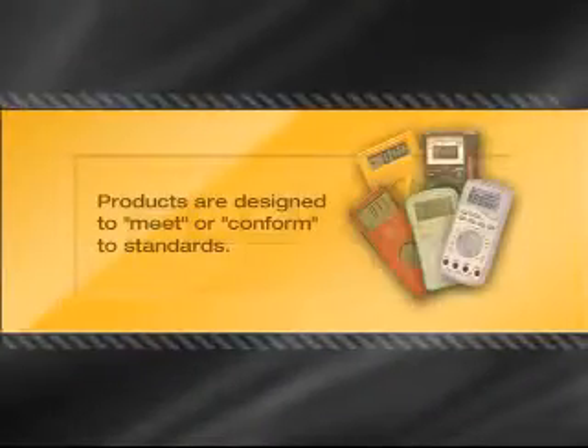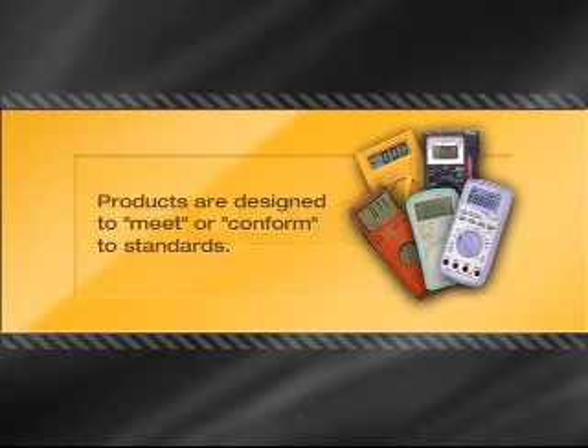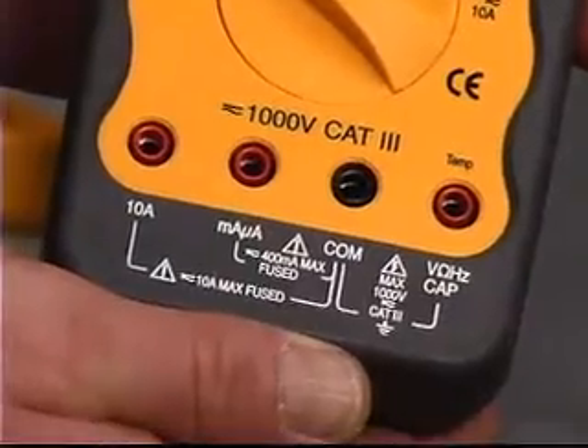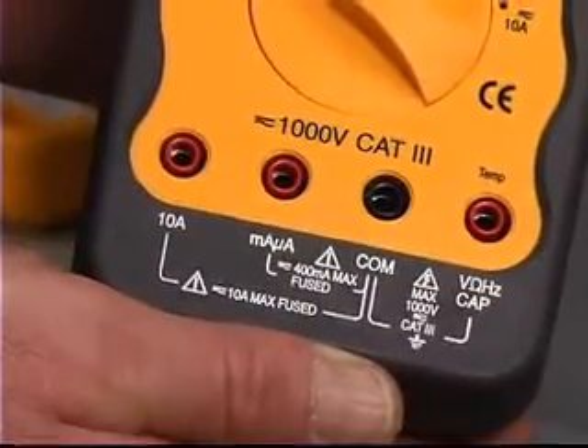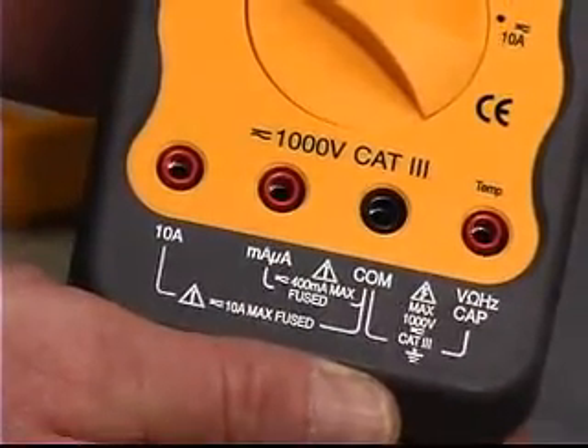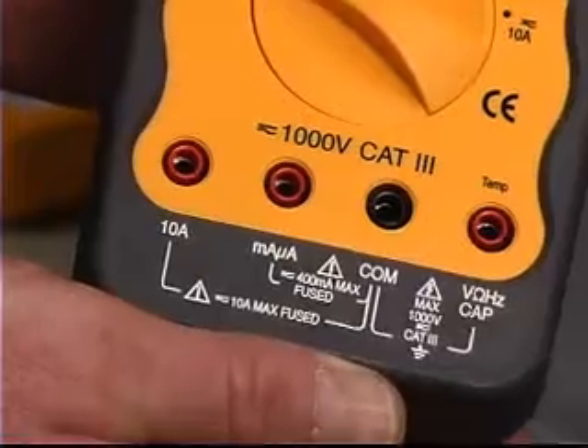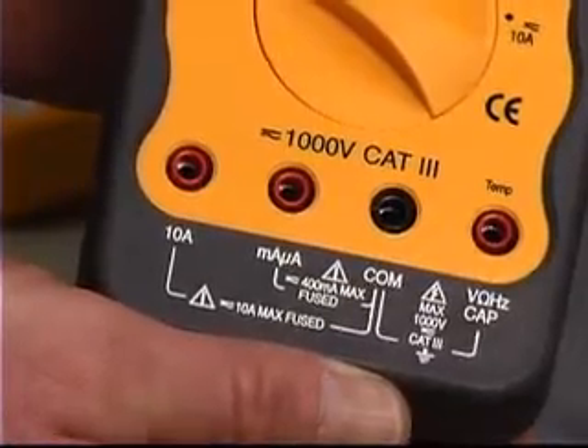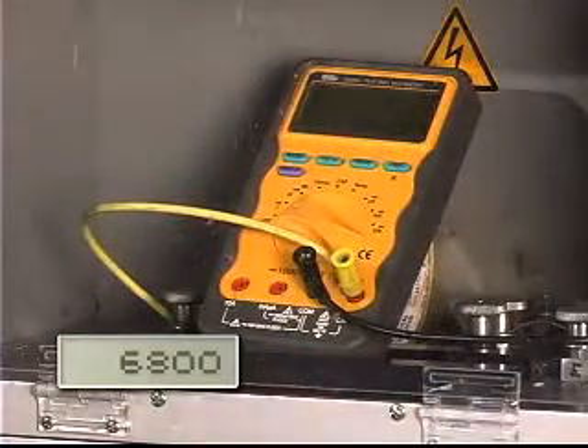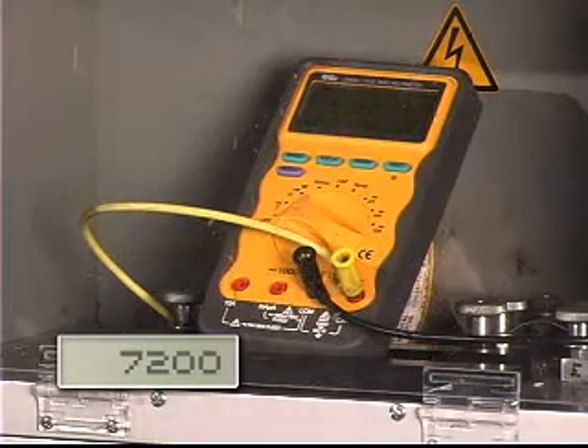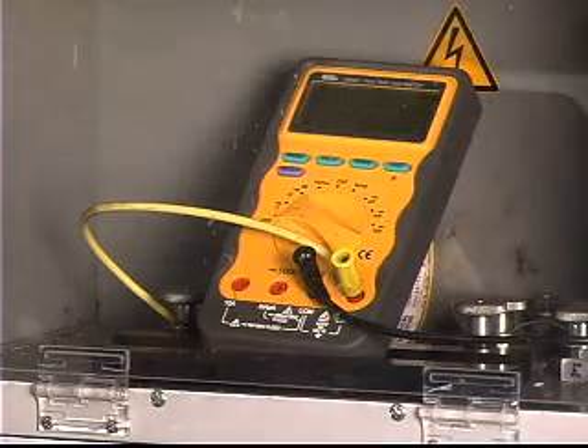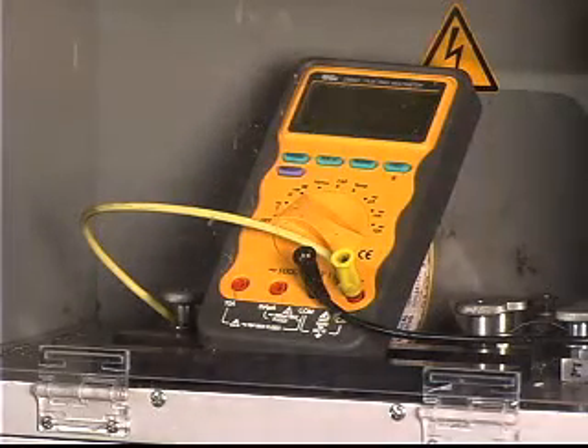Some manufacturers state that their products are designed to meet or conform to standards, but not every meter or tester that makes that claim will pass the test. Here's what happened when one meter, marked 1000 volts Cat 3, was actually tested. The meter is supposed to withstand a minimum of 20 transients of 8 kilovolts each, but this meter failed twice before reaching the 8 kilovolt minimum level. If this had happened on a power circuit, the results could have been disastrous.